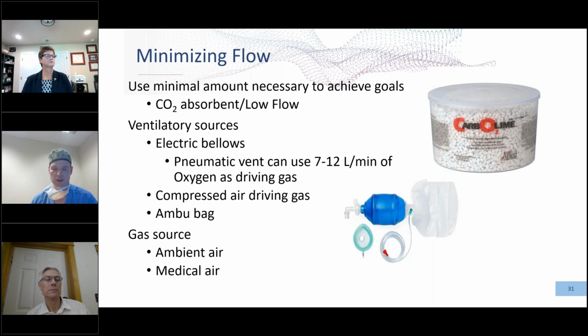A lot of these things I've listed here are things that you may not readily have available, but if you're in the planning phases, or your hospital is preparing for contingency operations, these are things that are worth exploring. So anesthesia machines, and there are ventilators for ICU patients as well. Anesthesia machines in particular were designed to be closed circuit systems that allow you to go low flow. The biggest barrier to low flow with most ventilators is just the CO2. If you're going so low on the flow, people just rebreathe their CO2 and they become acidemic and hypercarbic.